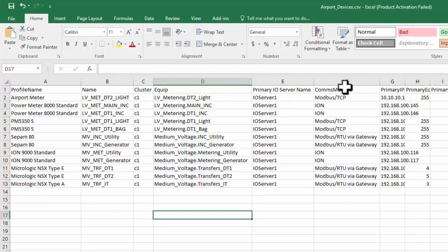IEC 61850 defines a standard method for gathering onboard waveforms through FTP. Similarly, Schneider Electric ION meters can provide waveform data via ION protocol. Other protocols do not specify a standard location for waveforms, so we are limited to what has been explicitly programmed in the drivers.